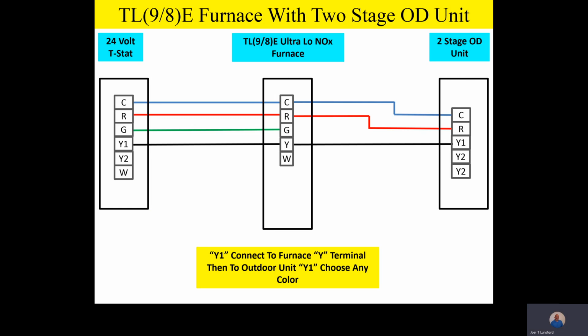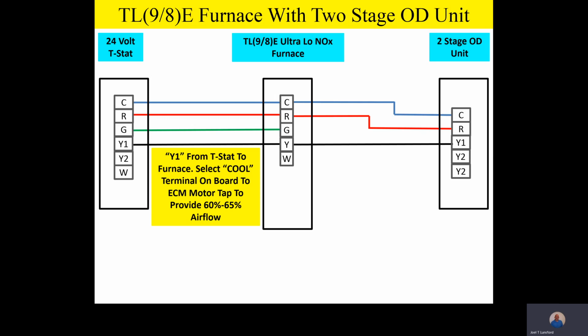Now, in order to have our cooling call, we're going to connect Y1 from the thermostat to the Y terminal on the furnace and then go straight outside to Y1. So Y1 from the thermostat to Y on the furnace to Y1 outside. Now remember, team, this is going to be our first stage compressor and our first stage cooling call.